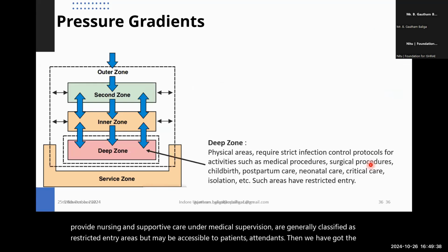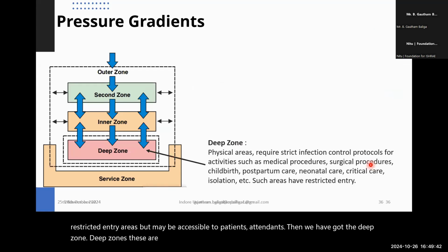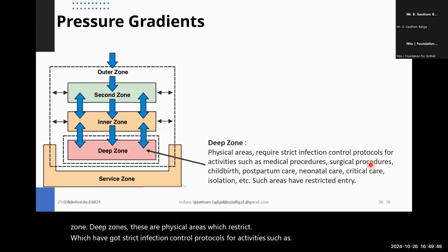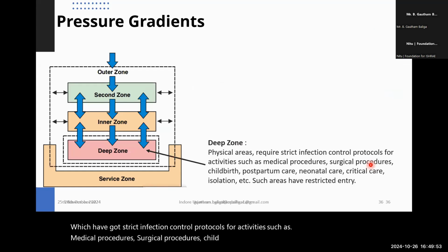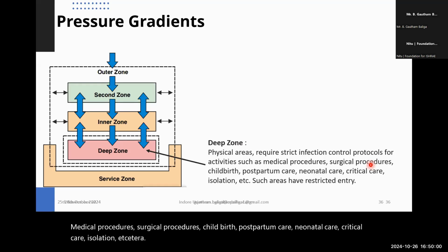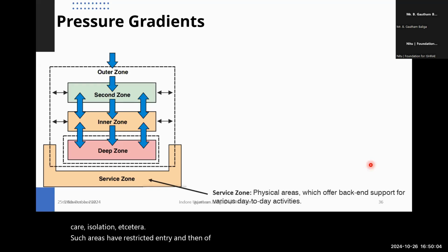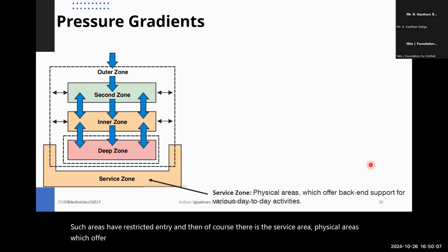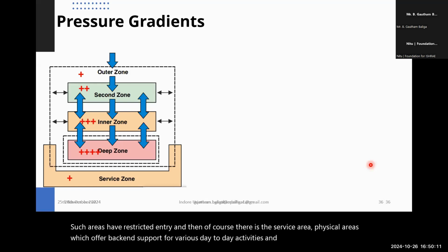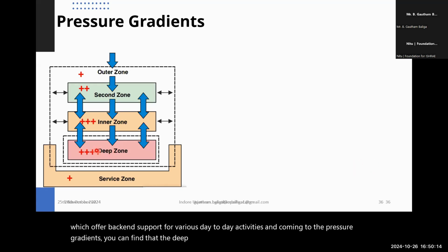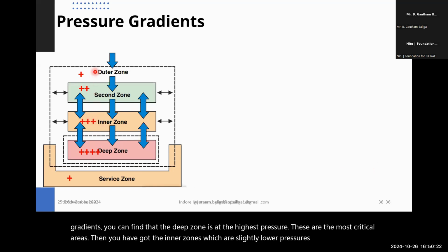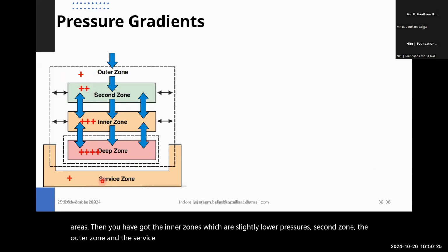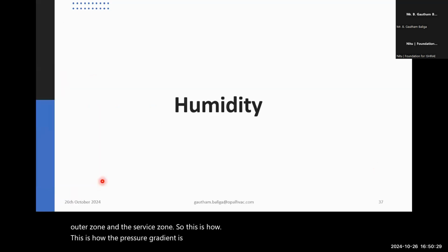Then we have got the deep zone. Deep zones are physical areas which have got strict infection control protocols for activities such as medical procedures, surgical procedures, childbirth, postpartum care, neonatal care, critical care, isolation, etc. Such areas have restricted entry. And then, of course, there is the service area, physical areas which offer back end support for various day to day activities. And coming to the pressure gradients, you can find that the deep zone is at the highest pressure. These are the most critical areas. Then you've got the inner zones, which are slightly lower pressure. Second zone, the outer zone, and the service zone. So this is how the pressure gradient is distributed all over the hospital.